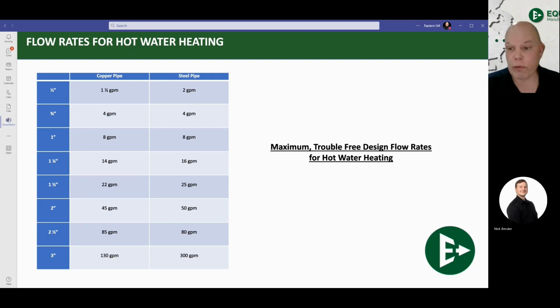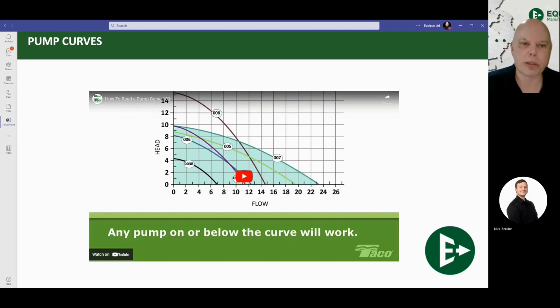When you go back to your universal hydronic formula of BTU equals GPM times delta T times 500, you will then see what sort of GPM is required to carry what amount of BTUs you want to put into a room. So if you do the math and you figure out that you need 4 GPM, that 3/4 inch pipe, 4 GPM is the maximum that we allow for 3/4. Maybe you want to upsize to 1 inch, maybe you're fine with 3/4. But there are going to be options for you, and these charts are designed to give you this information as to max BTU carrying and max flow rate through these pipings.